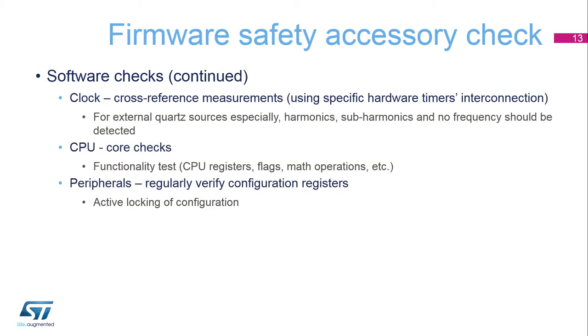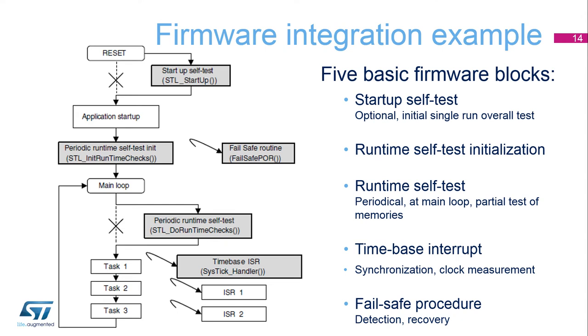Clock cross-reference measurements can use dedicated timer interconnections. The proportional ratio between two independent clock sources has to stay within an expected range. One frequency is used as timer input, while the other gates the timer input and raises timer capture events. A specific set of instructions can verify the CPU unit and its registers. For peripherals, it is suggested to verify the correct configuration at regular intervals. In principle, self-test procedures are included as an additional task when initializing the application main loop during system startup. This runtime self-test task provides periodic testing of the CPU, clock system, stack boundary, program flow, and both volatile and non-volatile memories.